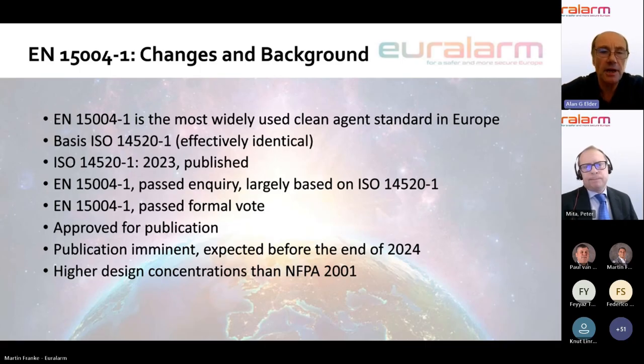I think most people are familiar that apart from the EN and the ISO standards, there is also NFPA 2001. And for those people who work outside of Europe, perhaps in the Middle East and parts of Asia Pacific, and certainly the United States, will be familiar with NFPA 2001. When people ask me for the key differences between 2001 and 15004, I say the one key difference is that there are higher design concentrations in the European and the ISO standard compared to NFPA 2001. There are a number of reasons for that, and that's not really the subject of today's webinar, but we'd be happy to talk through those differences on another occasion. So if you move on, please, Martin.